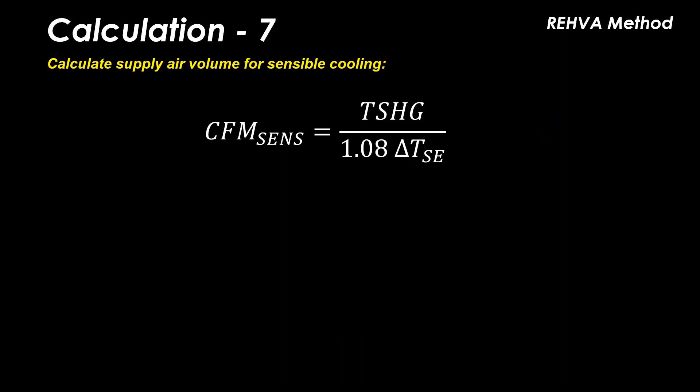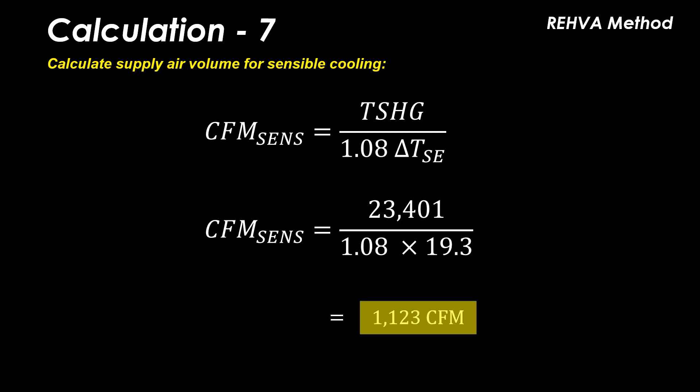The supply air volume to the space CFM sense can now be calculated by dividing the total sensible heat gains by 1.08 multiplied by the supply exhaust delta T, which results in 1,123 CFM.